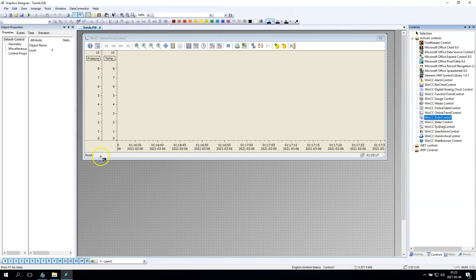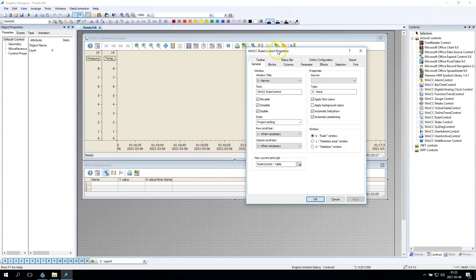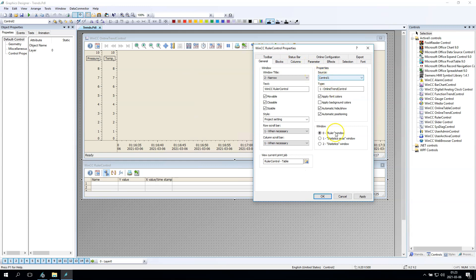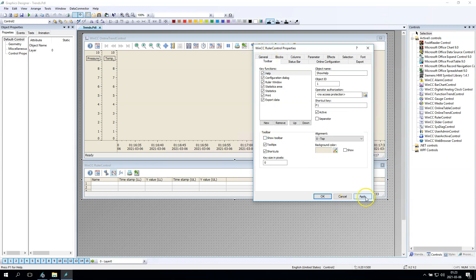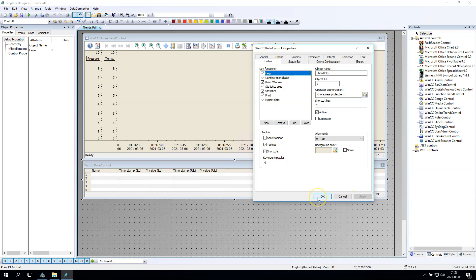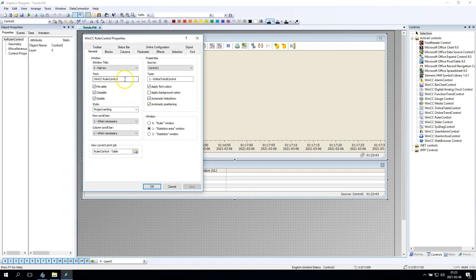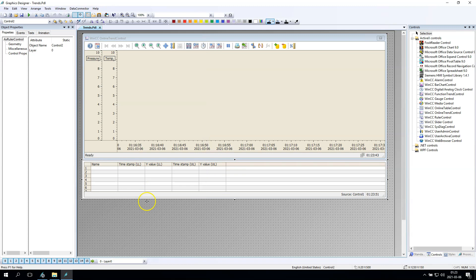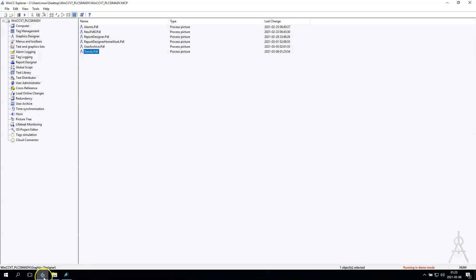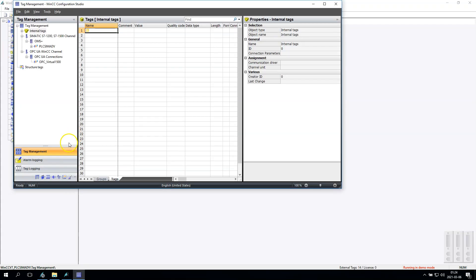Now we need to also put the WinCC Ruler Control. This ruler control has the possibility to set the source — the source comes from the WinCC Online Trend Control. If you have more controls you have the possibility to change the source to, for example, a second trend control. This control below will show you the names of your tags, the values, the timestamps, etc.